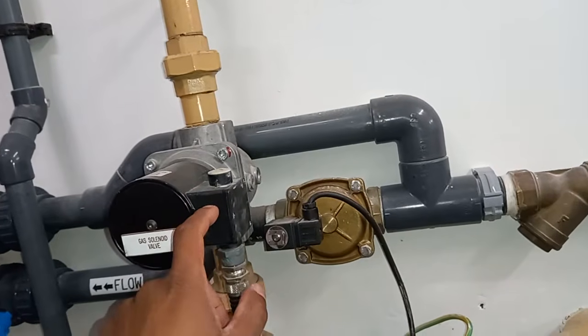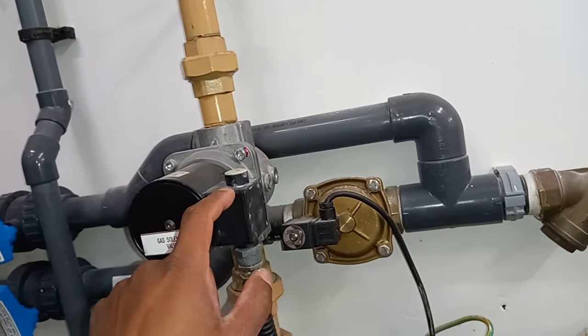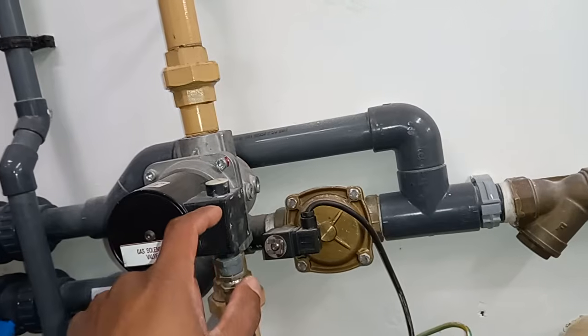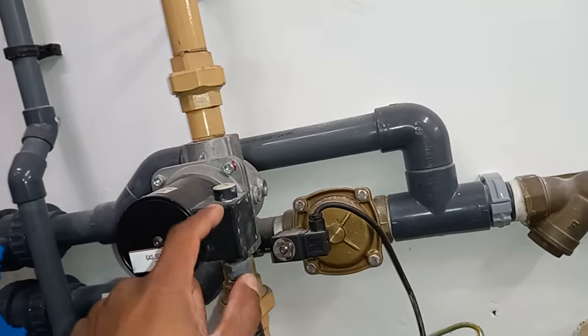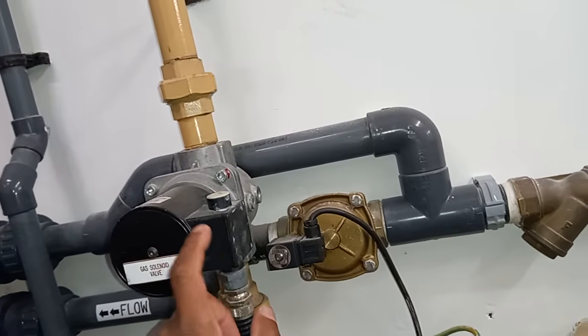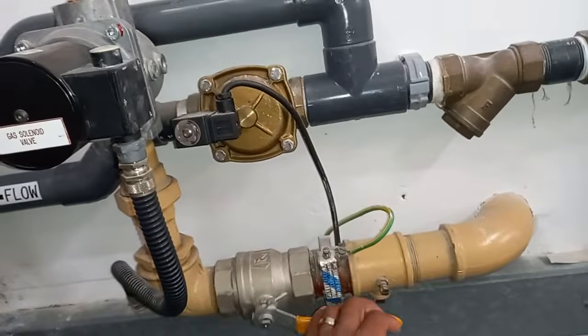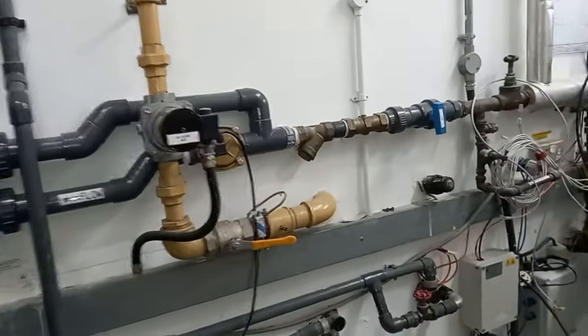I've seen plant rooms where these don't actually shut off the gas when the fire alarm or knock-off button goes off, which is quite strange, but 9 out of 10 times they do shut off during a fire alarm or safety knock-off. Let's see where the safety knock-off is in this plant room. Here it is, over here, the safety knock-off when activated.